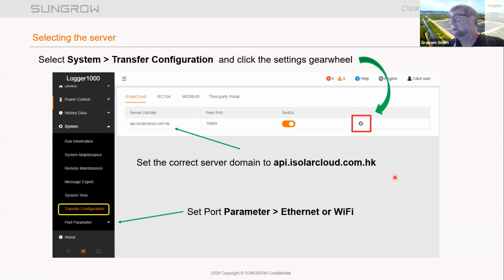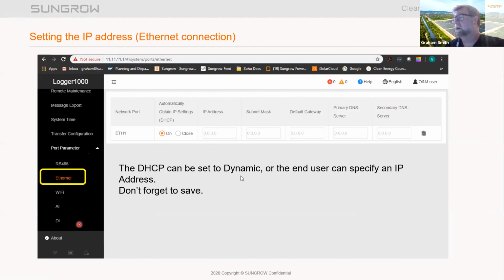Next thing you're going to do, and this is the Logger 1000 I'm doing, I'll do the IM4 in a moment. You have to connect either via the Wi-Fi or the Ethernet. So you select the port parameter, in this case Ethernet. This is if you're doing the Ethernet here. Now you have to speak to your customer. They might want to use a specific IP address, or they might not. DHCP is a standard default of most devices when you're connecting to the modem. You just plug and play. But if they have a specific IP address, then you just turn the DHCP off and you enter the IP address information in here, as per what the IT person tells you to do. And then at the end, this little floppy disk icon here is the save icon.